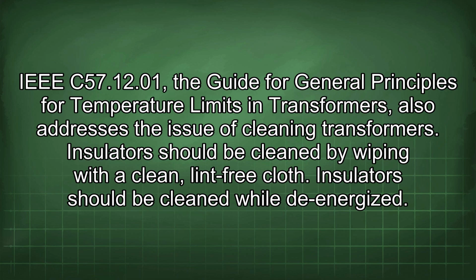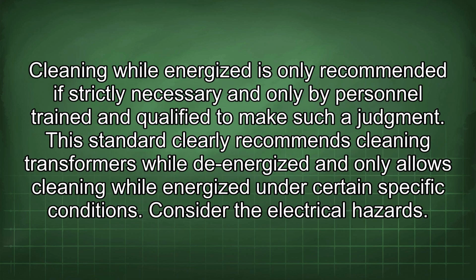IEEE C57.12.01, the Guide for General Principles for Temperature Limits in Transformers, also addresses the issue of cleaning transformers. Insulators should be cleaned by wiping with a clean, lint-free cloth. Insulators should be cleaned while de-energized. Cleaning while energized is only recommended if strictly necessary and only by personnel trained and qualified to make such a judgment. This standard clearly recommends cleaning transformers while de-energized and only allows cleaning while energized under certain specific conditions.